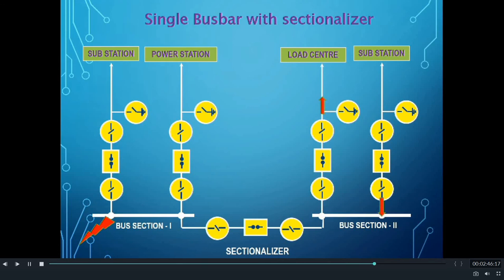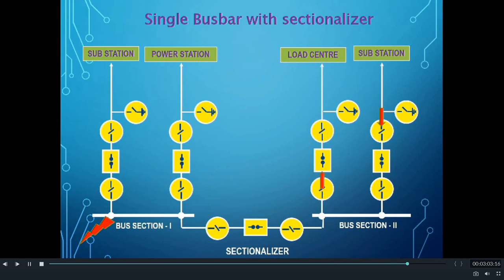Hence, when a Sectionalizer is equipped with only an Isolator, there will be an outage of all the feeders for a Bus Fault. On separation of the faulty Bus Section by opening the Sectionalizer Isolator, the healthy part of the Bus Section can run normally once again. But when a Sectionalizer is equipped with a Circuit Breaker, all the feeders are not interrupted for any Bus Fault — only the feeders connected to the faulty section are interrupted. Hence, Single Busbar with Sectionalizer is considered more reliable than the Single Busbar Scheme.